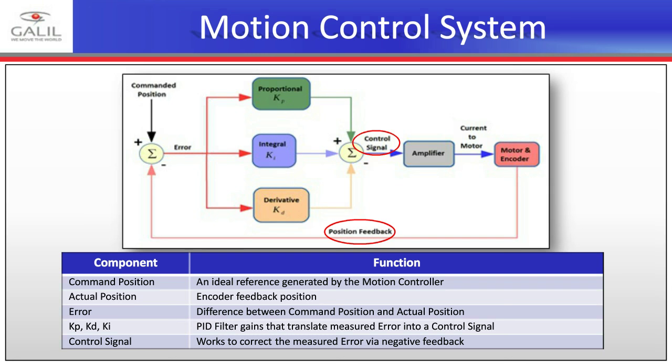Digital control of amplifiers involves taking that motor command signal — instead of an analog signal, you've wrapped position or torque data in a communication protocol, whether it be TCP, RS-485, Modbus, DeviceNet, or EtherCAT. Communication these days has become fast enough to make Ethernet communication virtually deterministic, meaning as soon as a packet is sent it's received and processed. I say 'virtually' because there is still a communication delay, but for the purposes of an application, as long as that delay does not add latency to the system, it shouldn't be a problem.